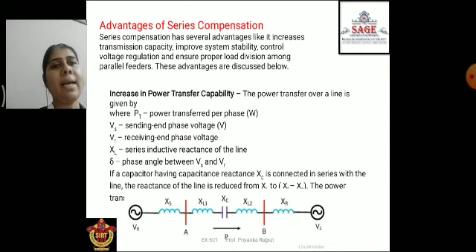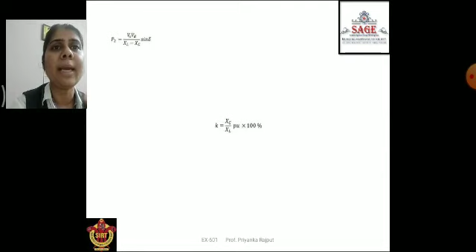Here P1 is the power transfer, Vs is the sending end voltage, VR is the receiving end voltage, XL is the series inductive reactance of the line, and delta is the phase angle between the sending end voltage and the receiving end voltage. If a capacitor having capacitive reactance XC is connected in series with the line, the reactance of the line is reduced from XL to XL minus XC. So the power transfer capacity is P2 equal to Vs VR upon XL minus XC sin delta.